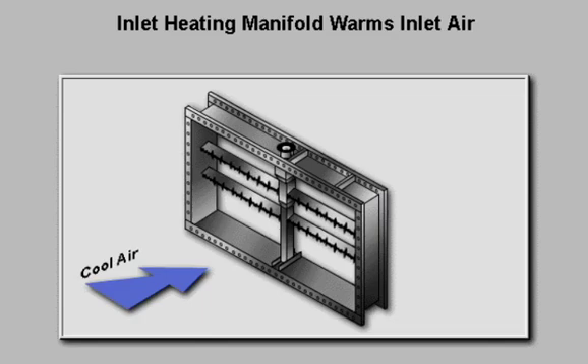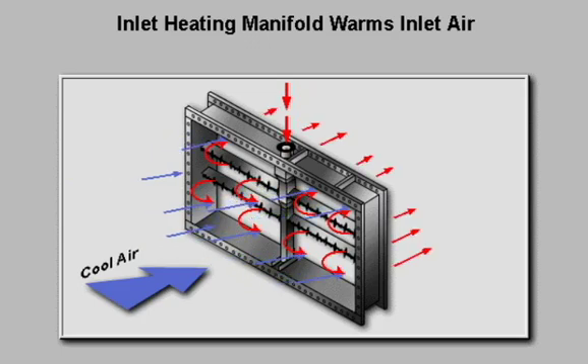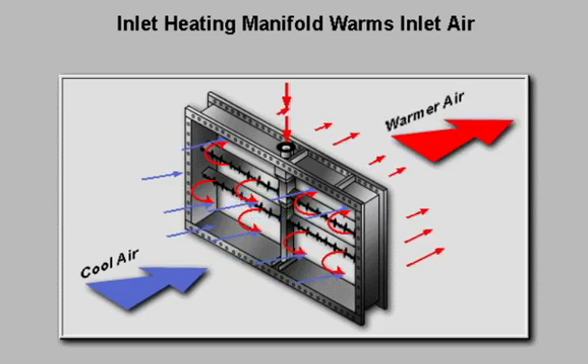The inlet heating manifold consists of a central vertical pipe with pairs of distribution tubes extending horizontally to both sides. During cold ambient conditions, compressor bleed air is forced through the distribution tubes into the inlet air stream. This warms the inlet air and prevents the formation of ice on the inlet guide vanes.